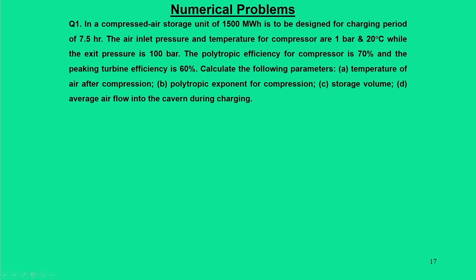We will now solve a numerical problem to get a feel for the quantitative numbers. This problem is about a compressed air storage unit designed for a charging period of 7.5 hours. Initial conditions: air at 1 bar and 20 degrees centigrade. Exit pressure is 100 bar. Polytropic efficiency for the compressor is 70 percent. The peaking turbine efficiency is 60 percent. We need to find: temperature of air after compression, polytropic exponent n, storage volume, and average volumetric air flow rate during charging.